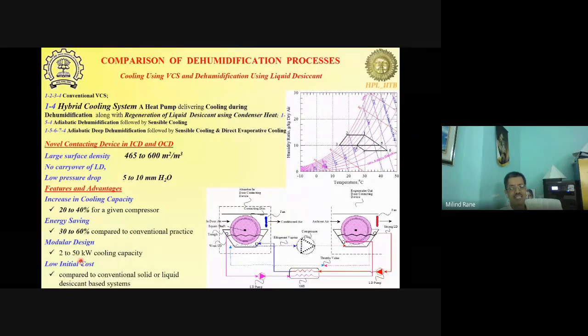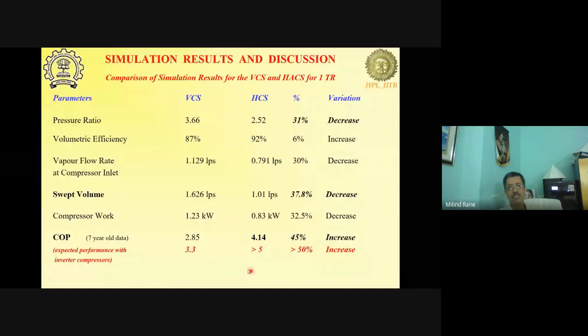Okay, modular units are possible, and COPs higher than this are possible. This is an integrated system. The liquid desiccant loop is shown here, and the vapor compression loop is shown here in between. Okay, so COP higher than 5 is possible, and that's because of reduced pressure ratio, improved volumetric efficiency, reduced volume displacement required for a given capacity, or decreased swept volume required for a given capacity, and so on and so forth. So that reduces the compressor size, increases the COP, and so on.